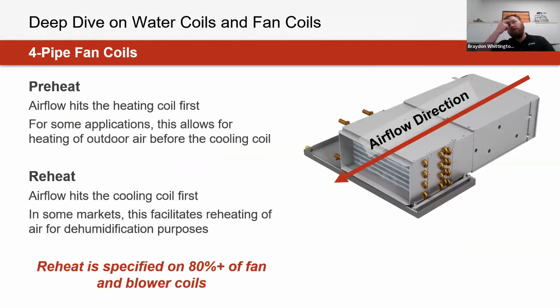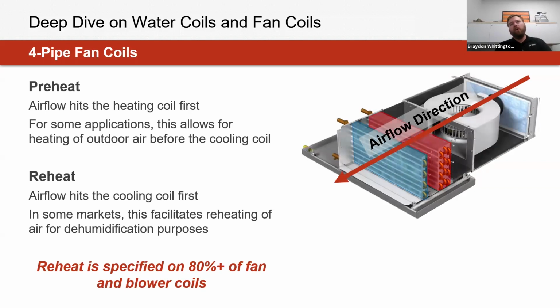Another key consideration when looking at fan and blower coils, what we'll see in some territories, I don't believe it's as applicable to your territory, but also 4-pipe configurations for fan and blower coils, where essentially it's going to have an individual coil for heating and another individual coil for cooling. But based off of where that heating coil is positioned and cooling coil is positioned, is going to dictate what terminology or verbiage is used for that configuration.